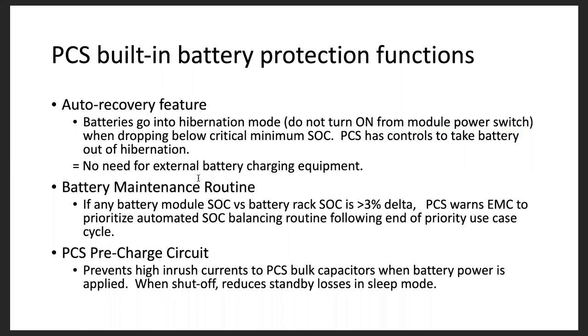So there's also a battery maintenance routine, as with most PV plus battery systems. The battery modules within the system are kept balanced within a few percent of each other. If any battery module SOC versus the battery rack SOC is greater than a 3% delta, it'll kick in that balancing routine. And there is a pre-charge circuit in the PCS that prevents high inrush currents to the bulk capacitors. Don't want to get too much into this. This is a little bit of a side note, but important as a service note if you have to turn the battery system off using the DC breaker; there's another slide later on that goes into a bit of that.